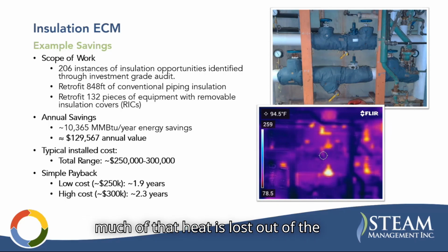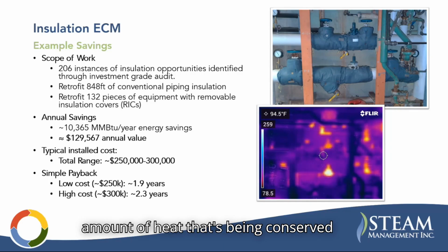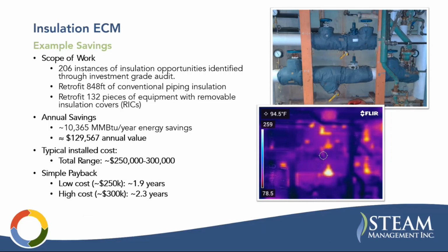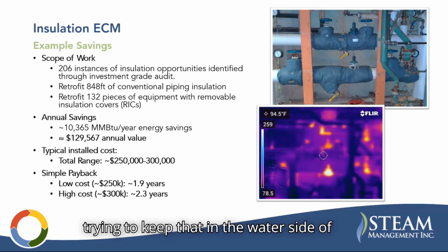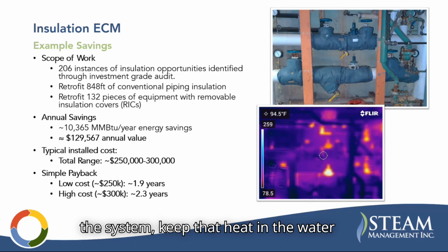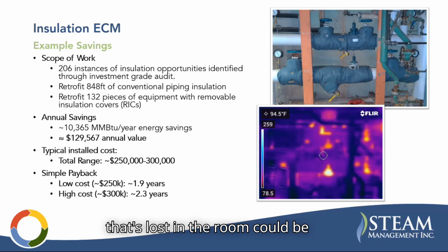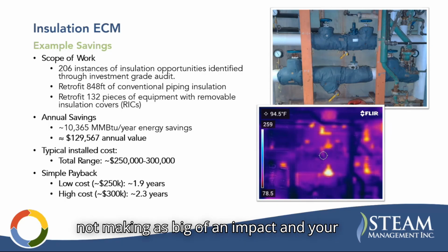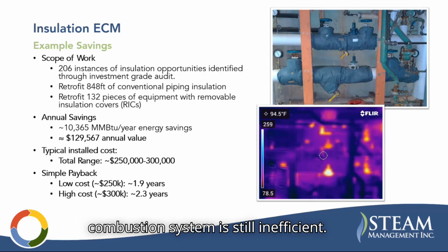I think so much of that heat is lost out of the room, though, through the walls and all, that I think you're getting a far less amount of heat conserved in your combustion air than if you just kept it in the system. I would definitely recommend insulating all of your components and keeping that heat in the water side of the system. But no, that's an interesting thought. Yeah, any heat that's lost to the room, you could be potentially recapturing, but you're not really getting all of it. It's not making as big of an impact, and your combustion system is still inefficient. So I don't know. I think it's probably not even close.